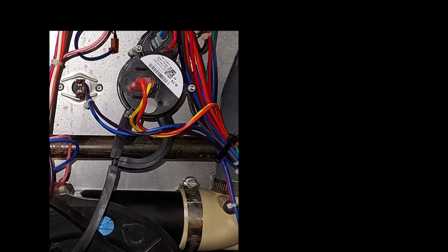And the pressure switch is a safety device. The contact points are normally open. So when the inducer comes on, the contact points close and send the signal down to the control board. But it is a safety device. For example, if the inducer motor doesn't come on, if it's seized, if the motor's bad, then it won't close that switch. So you don't want a furnace running without that inducer motor running.